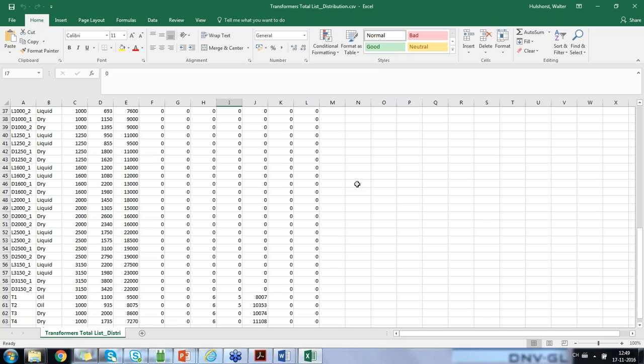What is the impedance of transformer and its impact on harmonics? Currently, I came across two 2 MVA transformers, one with 6.25% and the other with 9.05% impedance. In general, you can say, but it's very generic, that the higher the impedance will be, the higher the additional losses will be in the transformer. So you can imagine if you have two transformers with the same loading and the same rating, that the transformer with the high impedance normally will also have higher extra losses within the transformer.